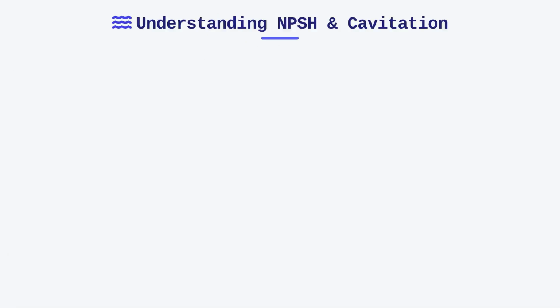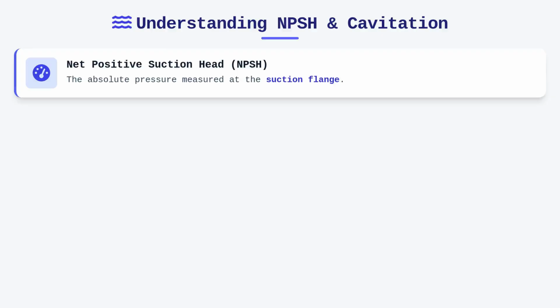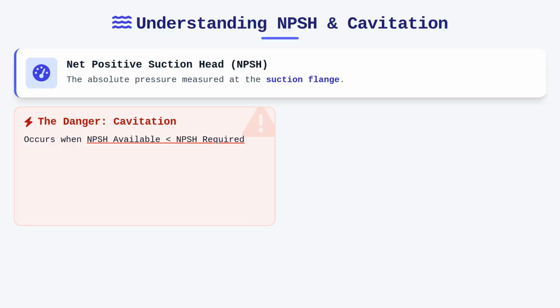Perhaps the most neglected aspect of pump design is net positive suction head, or NPSH, which is fundamentally a measure of the absolute pressure at the suction flange. If the available NPSH drops below the required NPSH of the pump, we encounter cavitation, which is the formation and subsequent collapse of vapor bubbles within the pump housing. This phenomenon is destructive, leading to pitting of the impeller, extreme vibration, and a catastrophic loss of hydraulic performance.